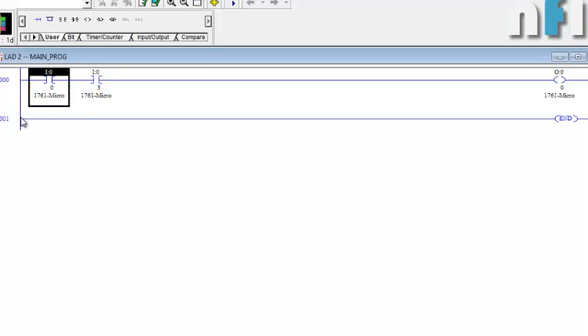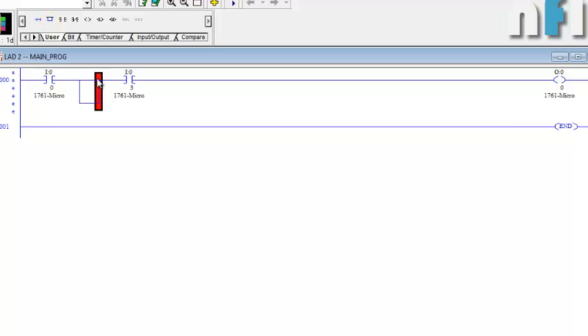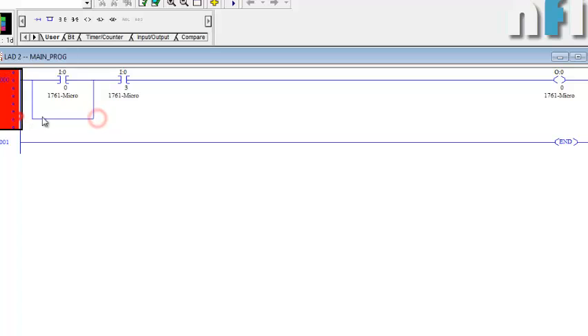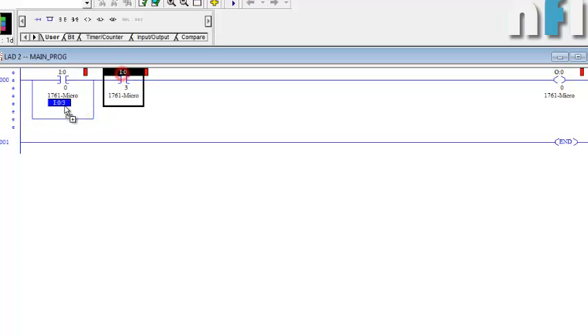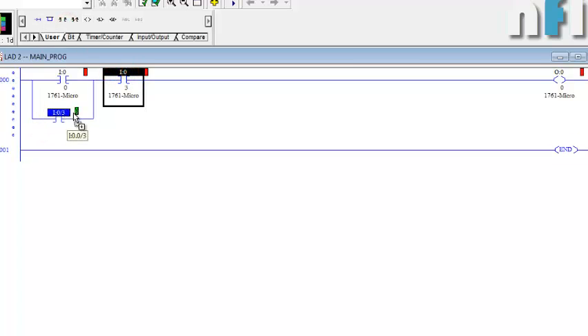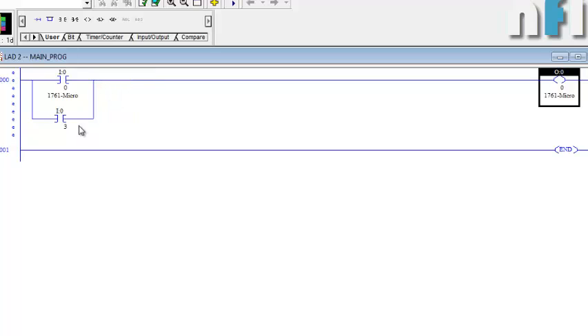Now to make an OR gate — where if any input is on the output is on — we need to connect inputs in parallel. In the ladder editor, click the rung branch button and place it here. Then add an NO contact in the branch and transfer the address. You can delete the old contact. This is the OR gate.